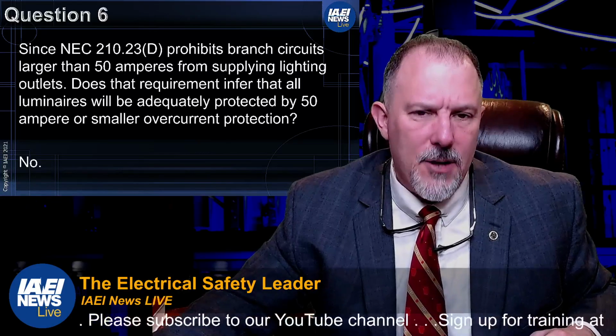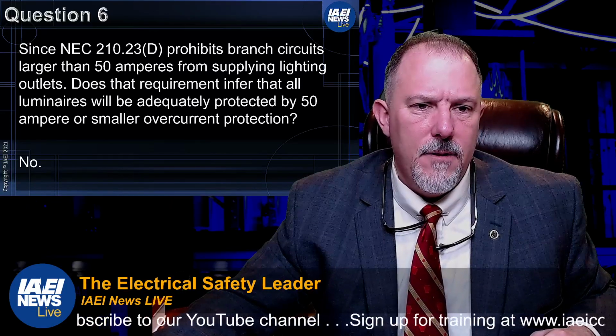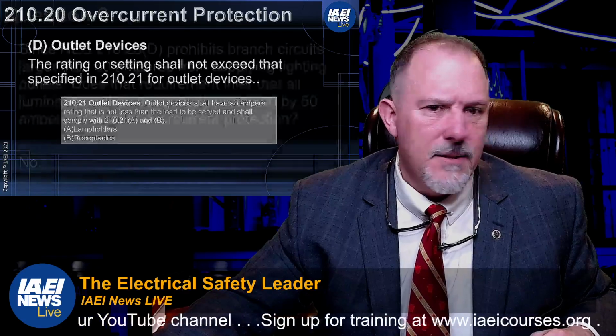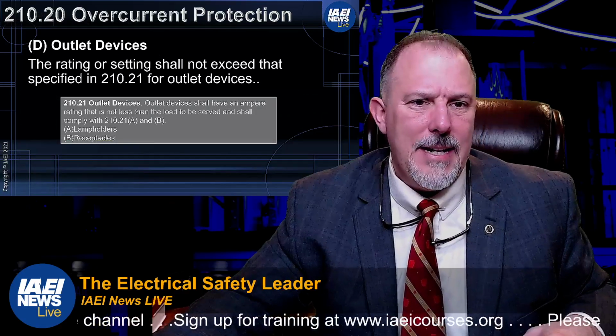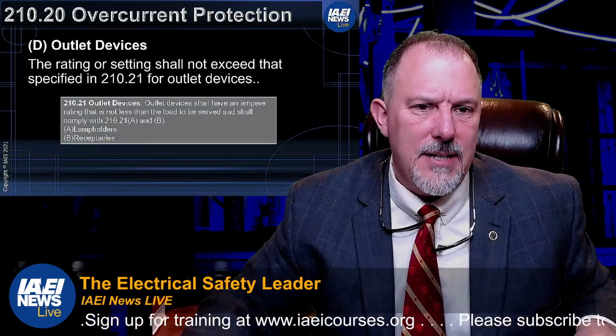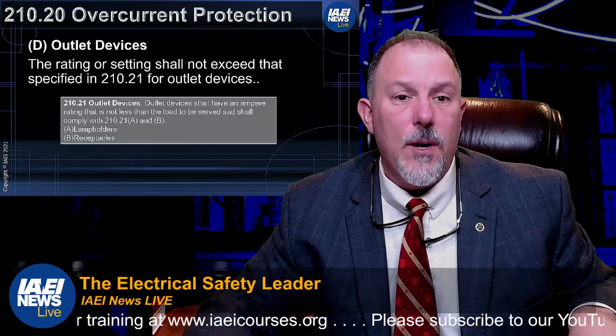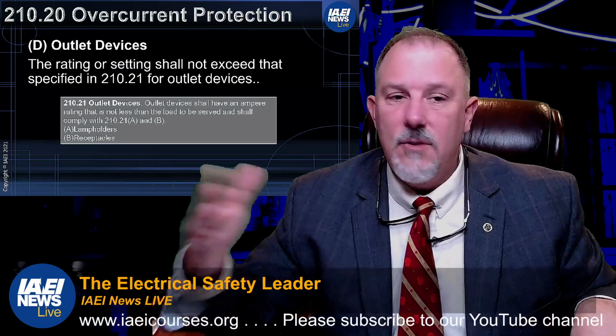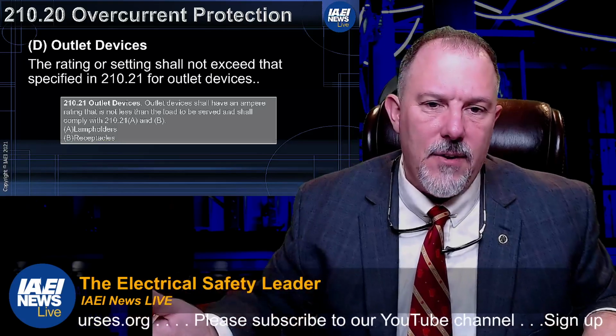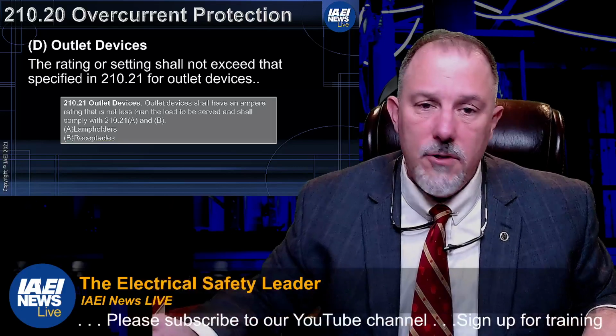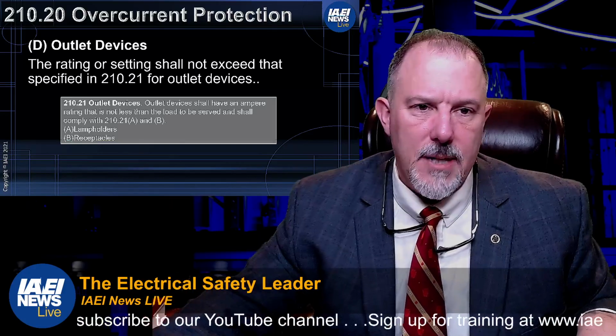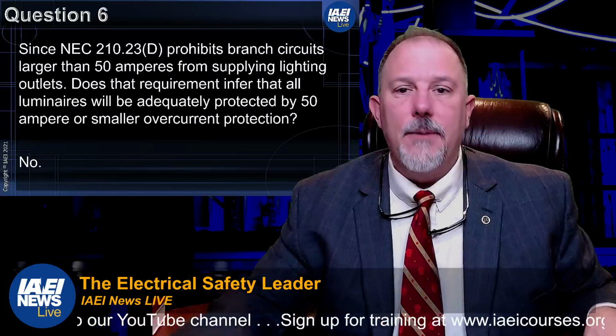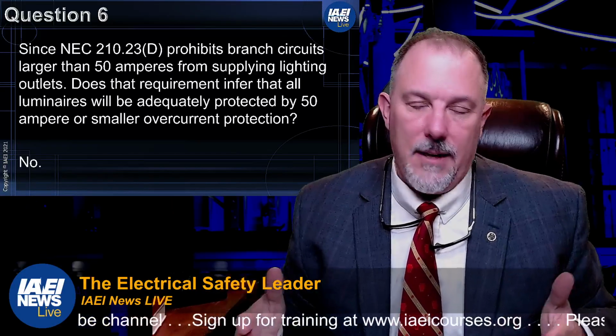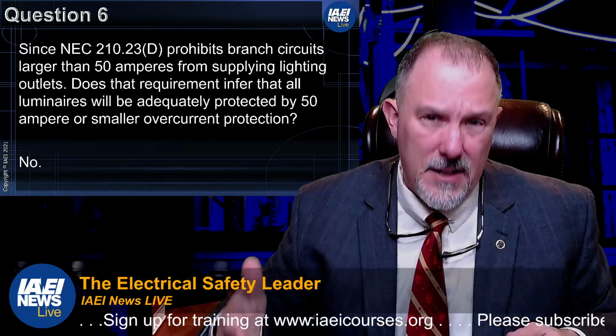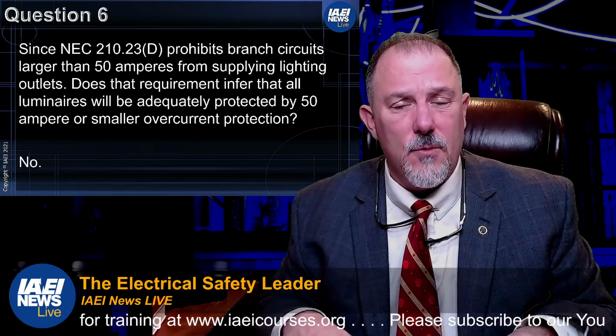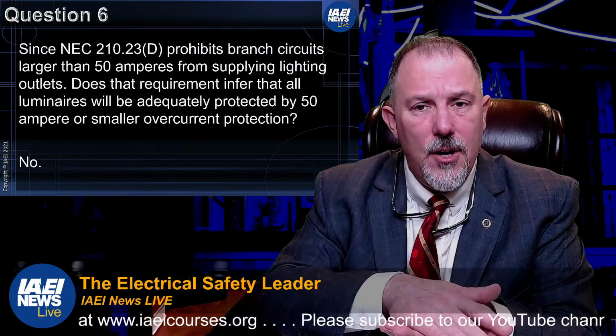All luminaires be adequately protected by 50 ampere or less. 210.20(D), outlet devices: the rating or setting shall not exceed that specified in 210.21 for outlet devices. And in 210.21, your outlet device shall have an ampere rating that is not less than the load to be served for lampholders and receptacles, etc. So I would say no, it doesn't guarantee anything. You've got to follow all of the different rules. And we just went through a lot of different rules, and we understand now how those products are.